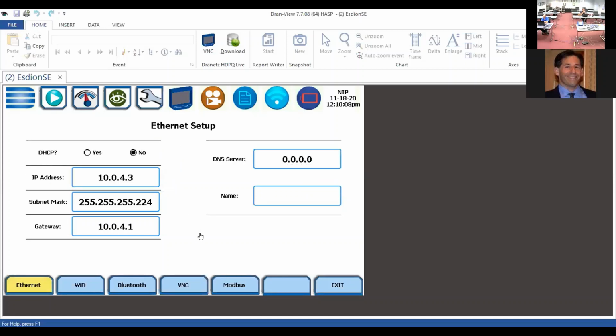and again, I'm doing this remotely, but if you're local to the instrument, you would simply do it locally on the instrument. So here in this setup you can see I'm using a static IP. I'm not using DHCP. Where I would use DHCP, I should say, is when you want the instrument to acquire an IP address from a DHCP server that might be on a local area network or a wide area network. In this case, I have a static IP address, which I've assigned to the instrument. It comes with the subnet mask and the gateway. That's all I need as far as setting up an IP address for the instrument.